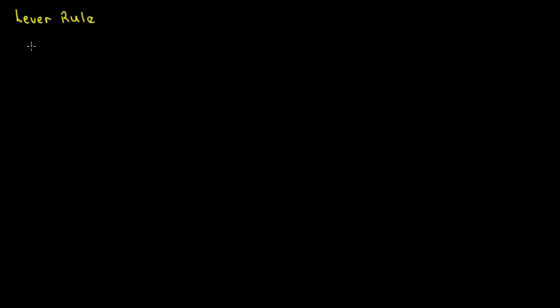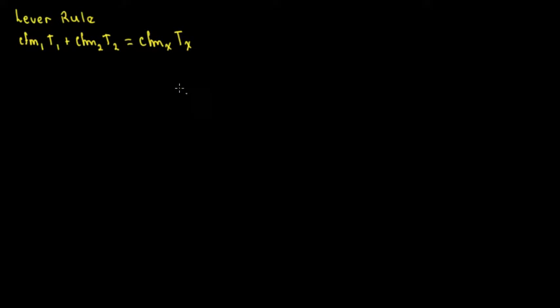So what's the lever rule? We're going to put in here the CFM and the temperature. This is related to the return air and outside air, how they mix and how the supply temperature ends up being. The formula is CFM1 × T1 + CFM2 × T2 = CFMx × Tx. That's the lever rule.